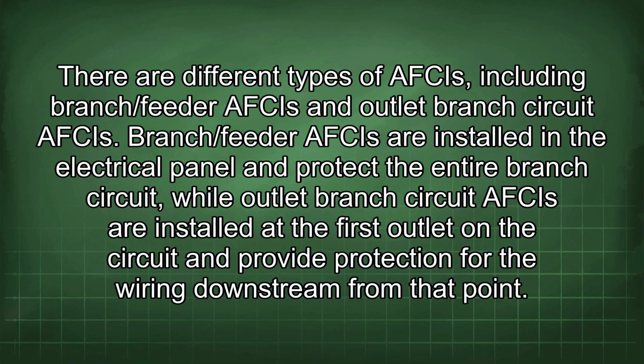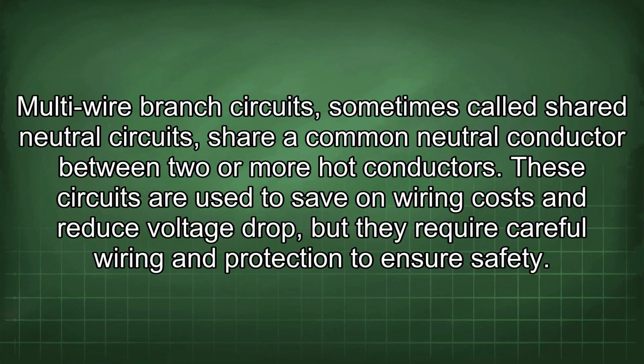There are different types of AFCIs, including branch/feeder AFCIs and outlet branch circuit AFCIs. Branch/feeder AFCIs are installed in the electrical panel and protect the entire branch circuit, while outlet branch circuit AFCIs are installed at the first outlet on the circuit and provide protection for the wiring downstream from that point. Multi-wire branch circuits, sometimes called shared neutral circuits, share a common neutral conductor between two or more hot conductors.